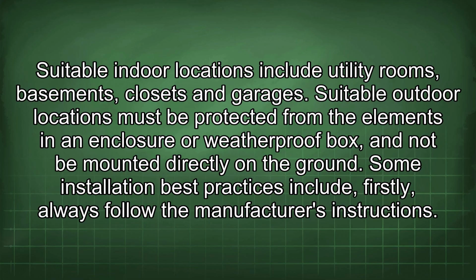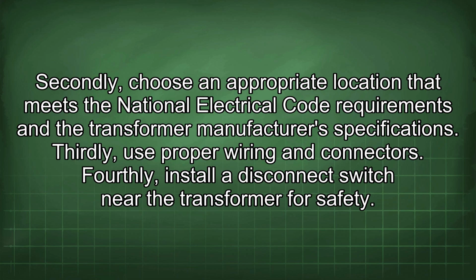on the ground. Some installation best practices include: firstly, always follow the manufacturer's instructions. Secondly, choose an appropriate location that meets the National Electrical Code requirements and the transformer manufacturer's specifications. Thirdly, use proper wiring and connectors. Fourthly, install a disconnect switch near the transformer for safety.